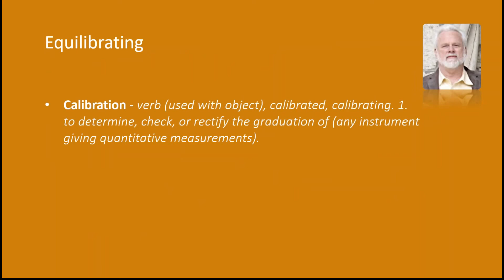So equilibrating. The definition of calibration is to determine, check, or rectify the graduation of any instrument giving quantitative measurements. Because we're trying to measure the force exerted by the animal, calibrating in volts is not actually calibrating. The best we can hope for in this approach is equilibration. That is, making the sensors from multiple stations produce the same output value for a known input force, or the same station, the same chamber, producing the same force repeatedly.